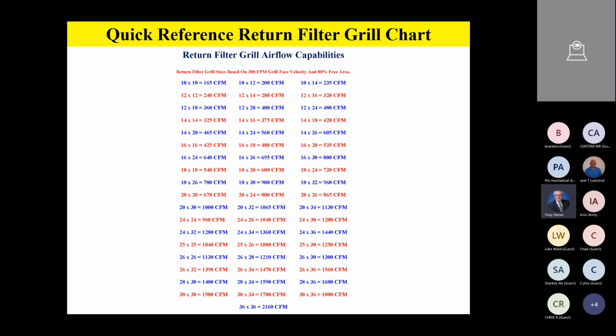Any questions on that? Yeah, Joe, we have a question from Curtis. What if your static pressure is good, but the customer isn't getting enough air to a room? But in order to cool that room, it puts the static in the gray area. What I'm going to recommend, if your total static is good through the system, remember if you put in a larger duct, a bigger takeoff, in other words, into that room, you'll actually provide more air. The other thing you can do if your static pressure is good for the entire system is put manual dampers, if possible, on the other takeoffs and start balancing it with those manual dampers. That would be a way to help remediate that or to push a little extra air into that one room. But the best thing to do if you need more air into a space, more volume, is to increase the takeoff duct size into that room.